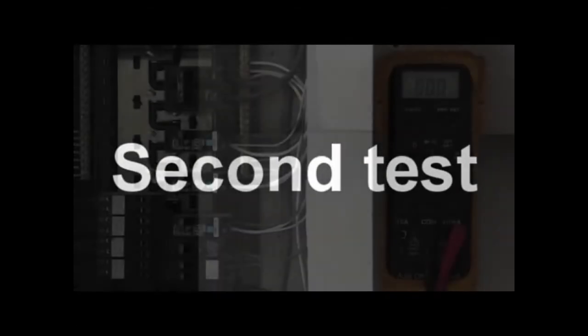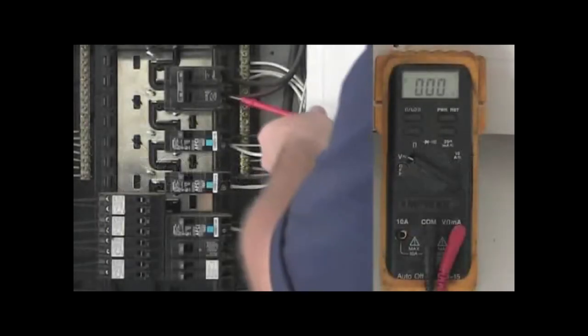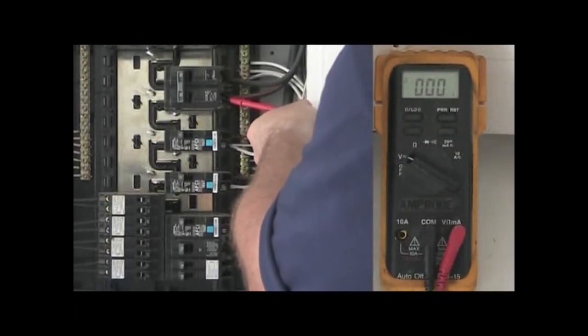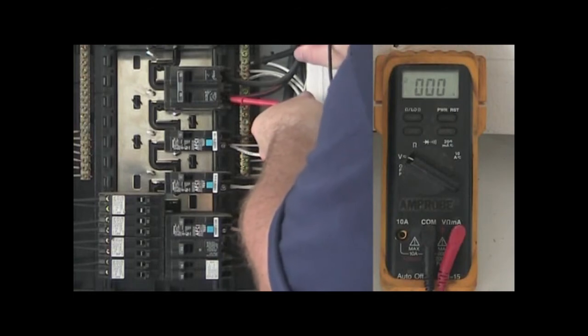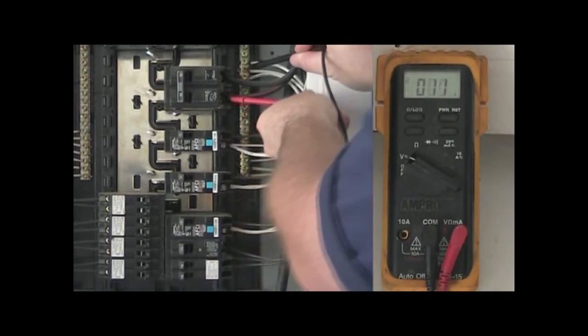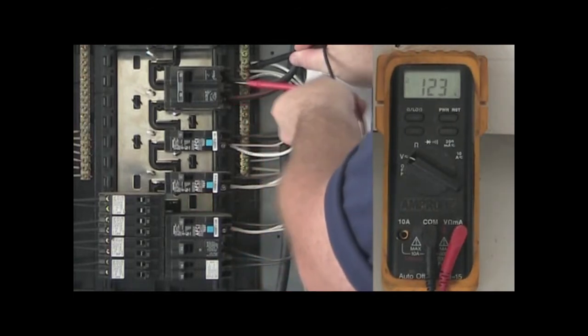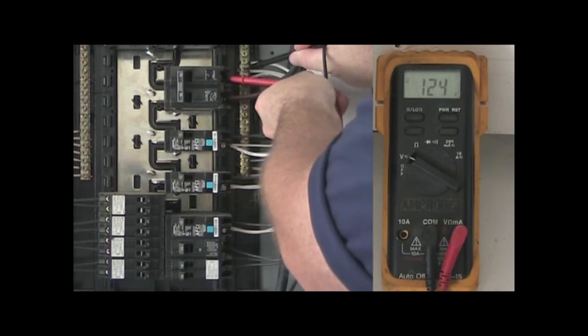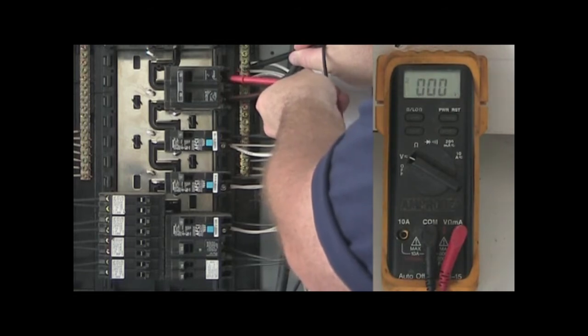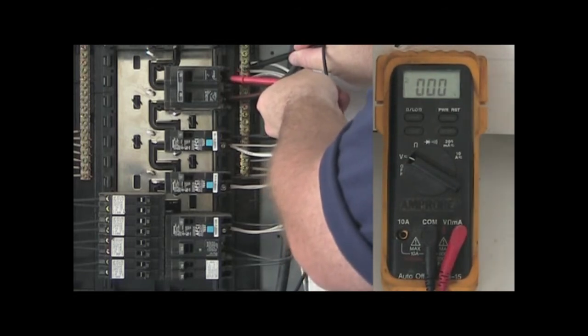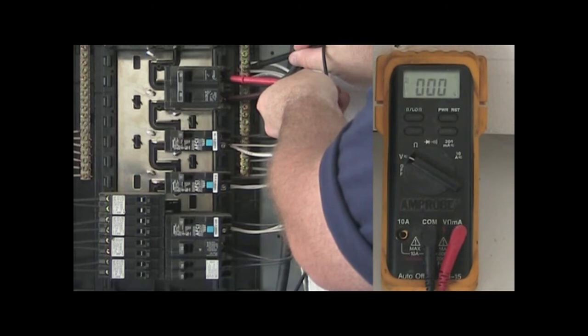For the second part of this test, you will leave the red lead on the breaker terminal and place the black lead on the neutral bar. Do this for both sides of a double pole breaker. If the breaker is bad or failing, one side will read 120 volts while the other side will read between 0 and up to 110 volts.